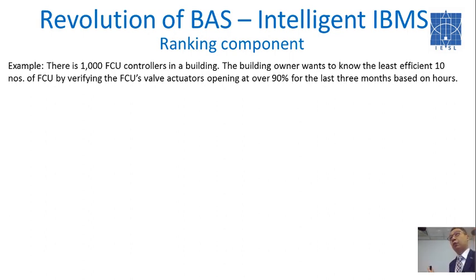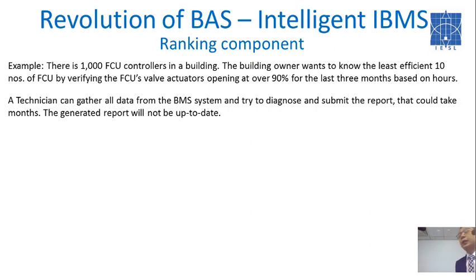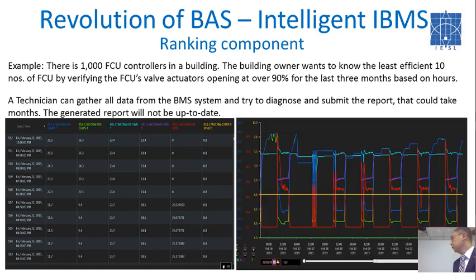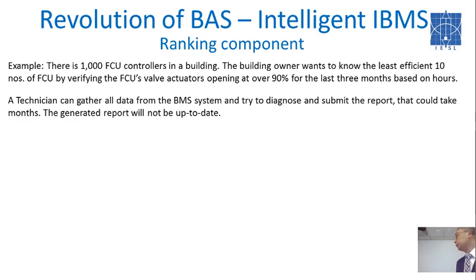So with these ranking components itself, I do not need my technicians to do routine servicing anymore. He will be proactive to rectify the concerns on the fan coils itself. So how do the technicians verify the reports? The technicians can gather all the data from the BMS through Diagnostic, data, trending, reports itself, but when he generates the reports, it will not be up to date because we are looking for 10 numbers out of 1,000 over the period of 3 months. When the report is generated, maybe it's 6 months down the road. So how does the ranking component work itself?